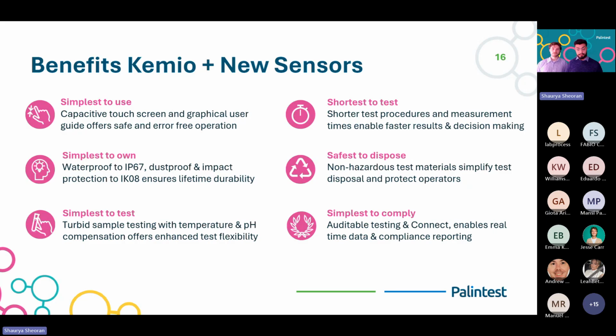And this is because we understand that the field operators are doing so many jobs in a day. For them, it's about getting to the water test, making a quick decision, moving on to the next task. An insight we had while developing this sensor was that the current methods to measure monochloramine are complicated and they are temperature dependent. The common photometric method's test time depends on the temperature. So if it's really cold weather, you might have to wait 20 minutes, whereas if it's hot water, you have to wait 2 minutes. And that does introduce error into the system because you have to make sure you're using the right test time at the right temperature all the time. Whereas with Kemio, you remove that temperature dependence because the sensors are already calibrated for that, which means you just spend 2 minutes and you are able to get that test result. So the procedure is very repeatable every time.